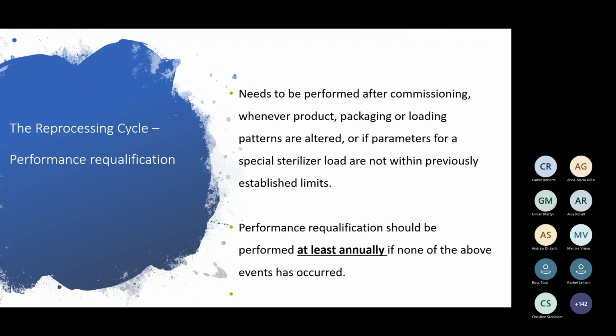So performance requalification should be performed at least annually if none of the above events has occurred. Sometimes if you have a major repair on your sterilizer, maybe the vacuum pump or something like that is changed, or the main circuit board, something like that, then the technician may say to you, you need to have a re-performance qualification done again.